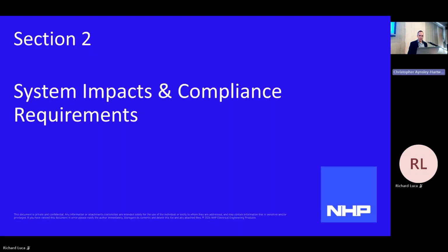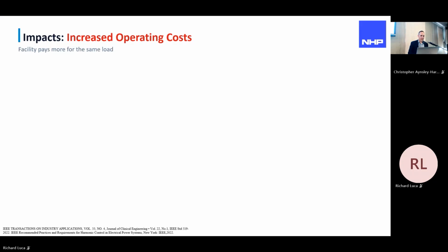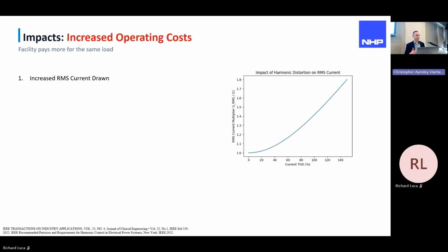System impacts and compliance requirements. So we're going to look at some impacts now with harmonic distortion, and it falls under the broad category of increased operating costs for the facility. We've got an increased RMS current draw. So there's a factor applied, an increase in THD. We apply a factor on the THD for the facility.